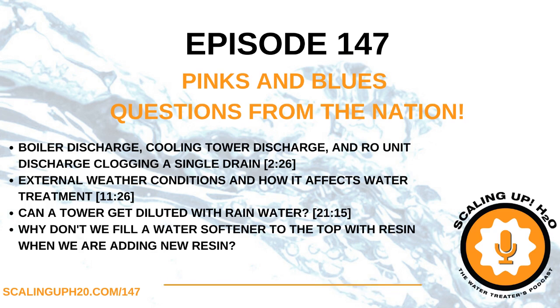Really? Is that true? And I'll tell you, 9 times out of 10, that's a lazy technician not finding out what the problem is. Because the first thing I do when I read something like that in a service report is I walk around the system. And 9 times out of 10, I normally find that the cooling tower is overflowing. Now, the technician might not have realized that because the cooling tower was on the roof and they do all their tests in the basement. Well, folks, you got to look at the equipment that you are servicing or you're not servicing that equipment.